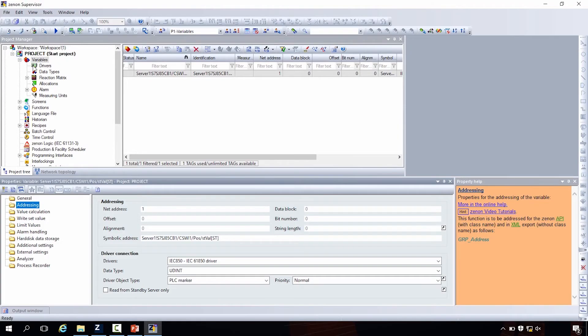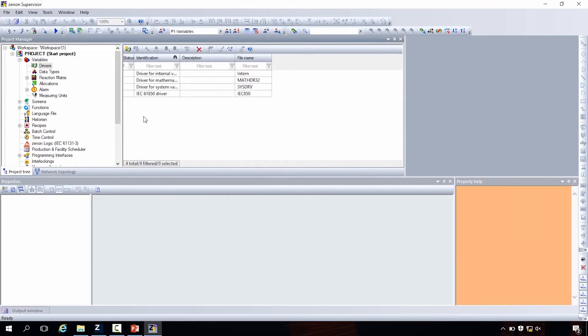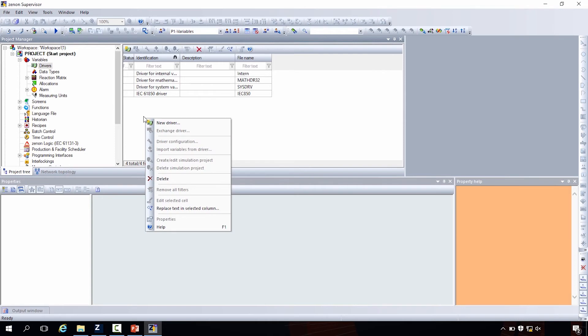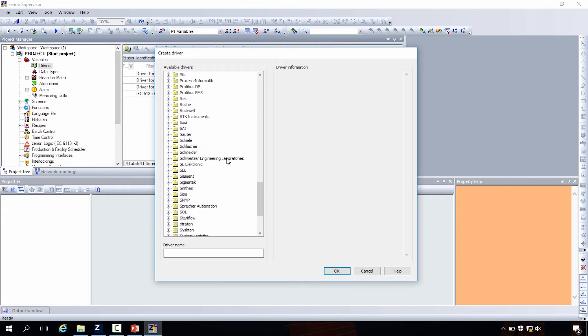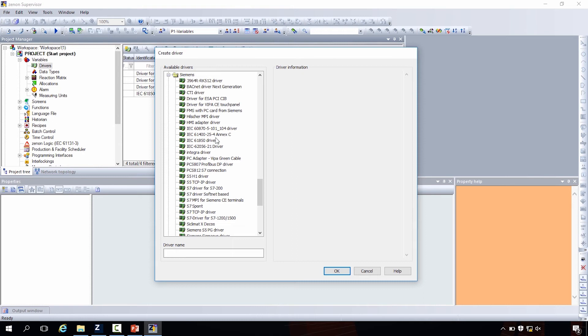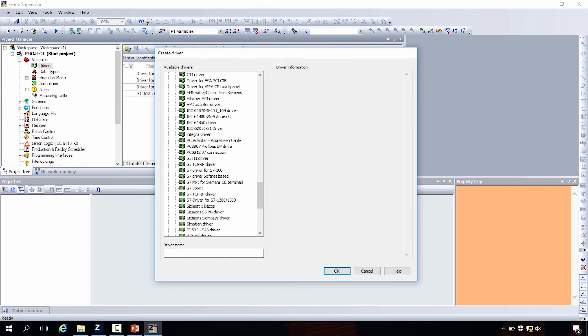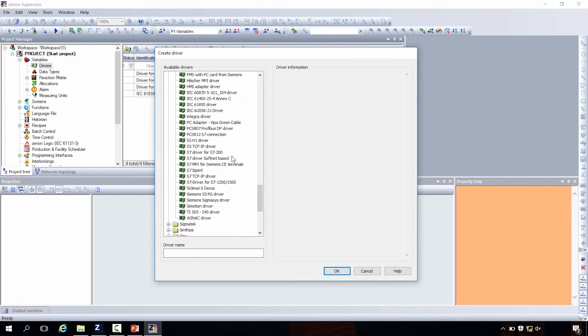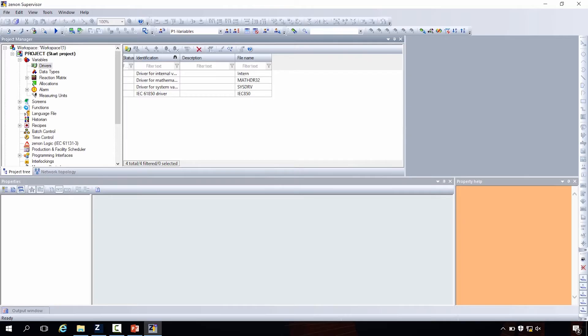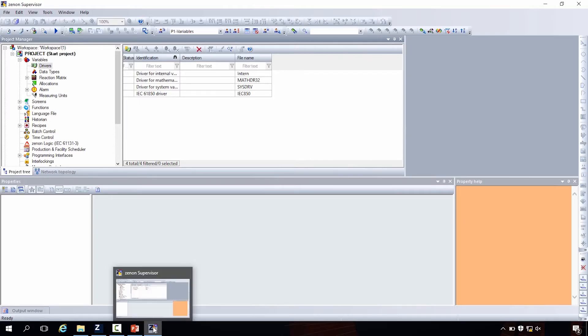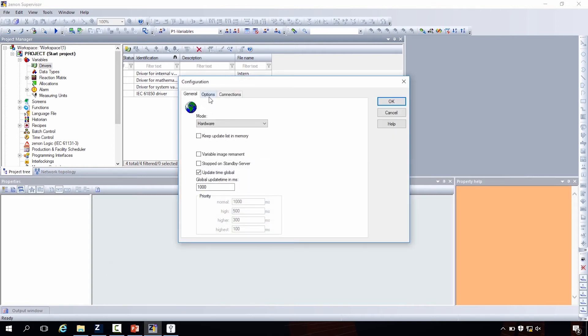As I showed before, first we need the driver of our choice. Actually we will find it in the Siemens S7-1500. Let's see in the drivers, create the driver first. Just follow the same procedure before. New driver. Here there is the Siemens S7-1500, where you find all related. Of course they have a lot of different hardware. And one of it is here. There's a S7 driver for S7-1200-1500. That's the driver of our choice. With OK I select that driver.